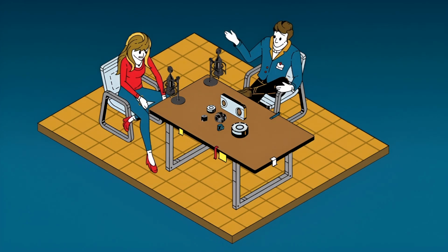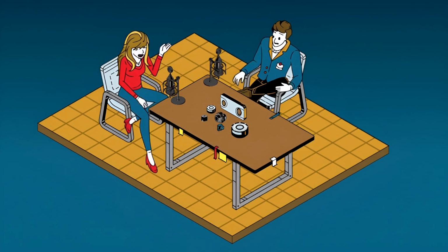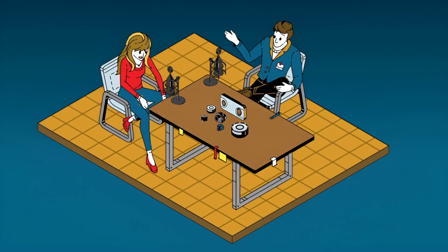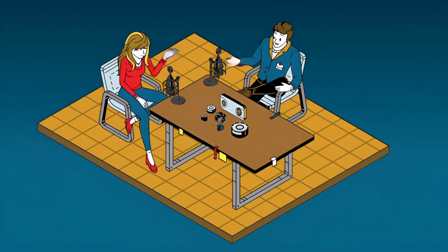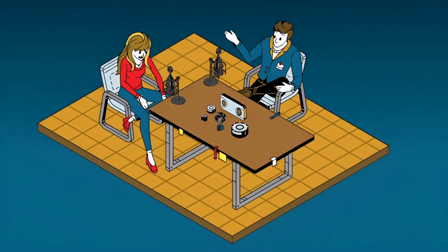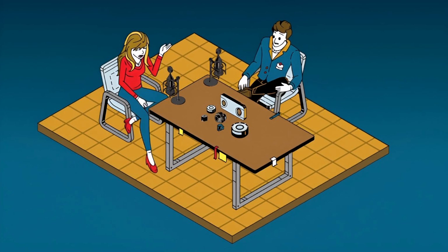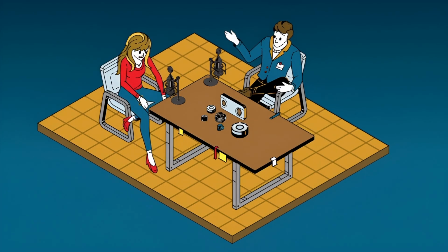Well, the core proprietary tech is really designed specifically to beat interference. When you're measuring forces on, say, a rocket structure, you're fighting all sorts of things: noise, vibration, big temperature swings. Standard sensors often just can't handle that environment reliably. And the sources point specifically to two critical design features. They're moment-compensated and temperature-compensated load cells.